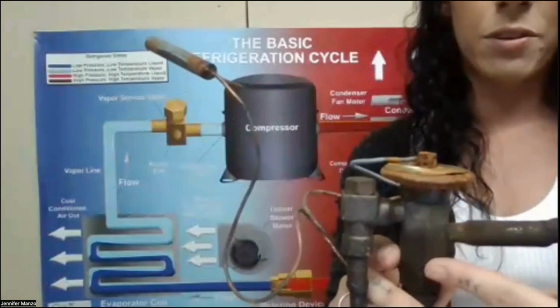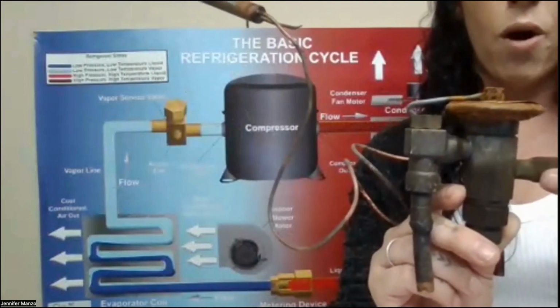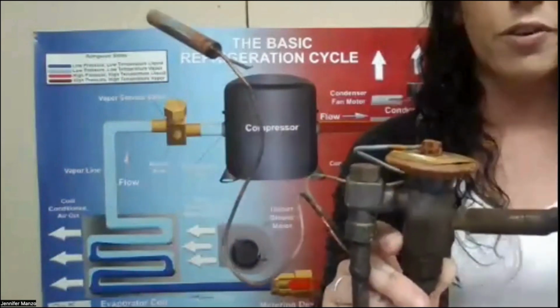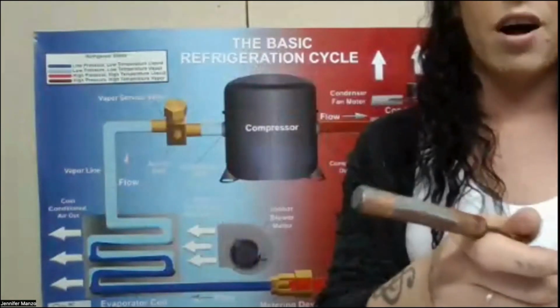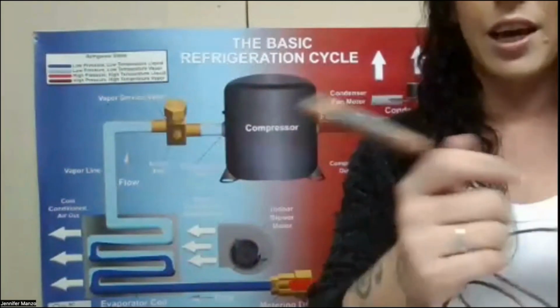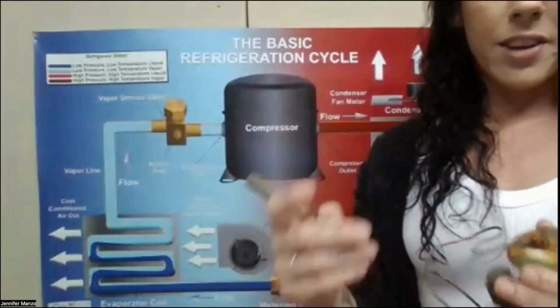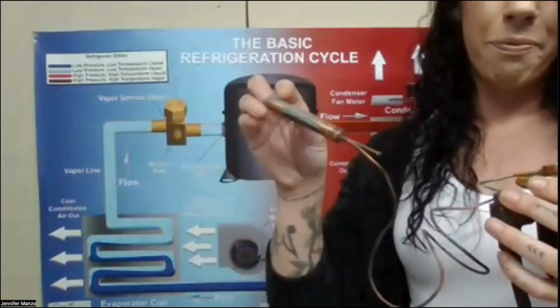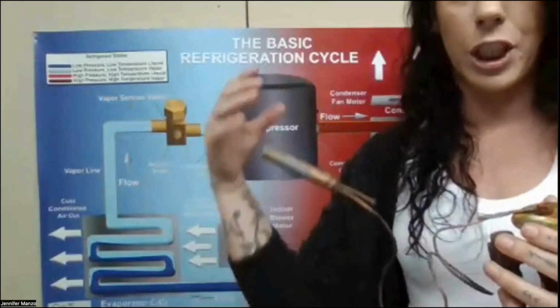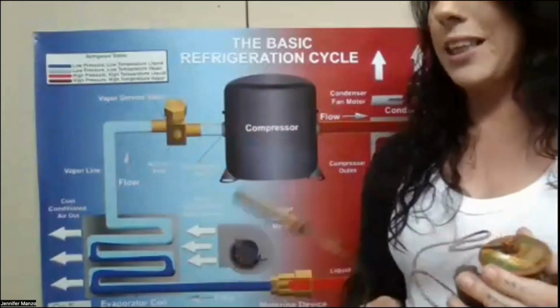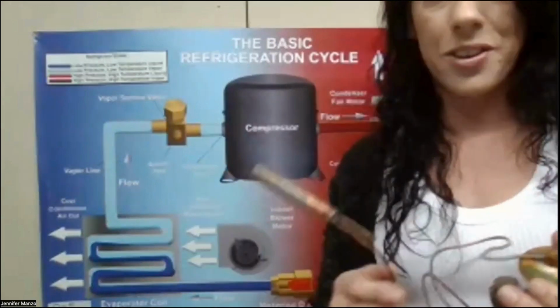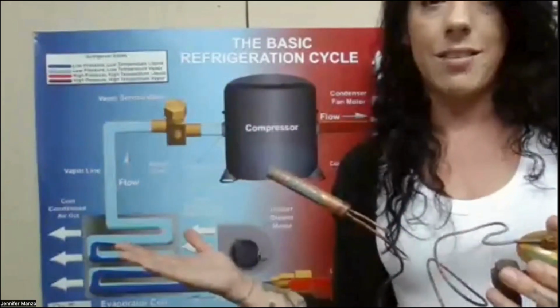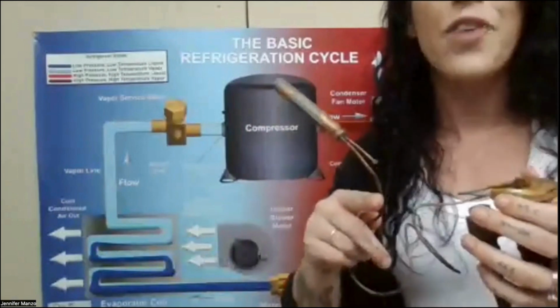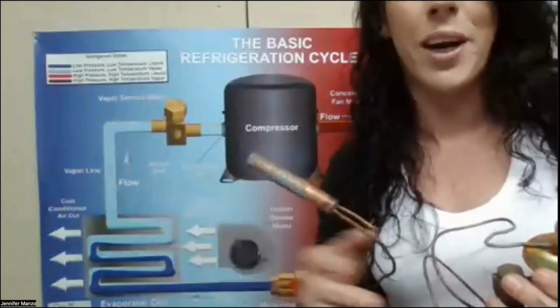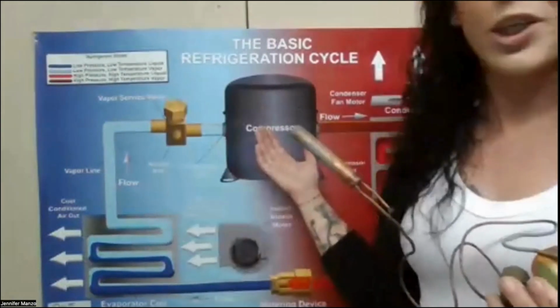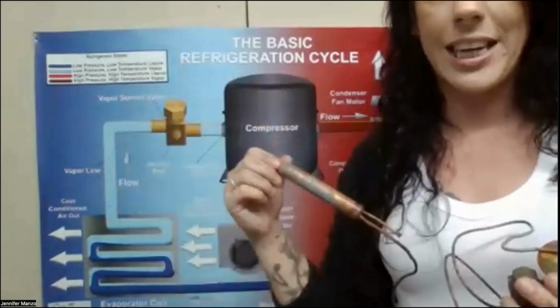The valve moves up and down to let refrigerant out or to not, to either give you more refrigerant or give you less refrigerant. And all of that is based on this sensing bulb. So the sensing bulb goes at the evaporator, and depending on what the evaporator temperature is, the sensing bulb bubbles. It boils, right? Because these refrigerants boil at such a low temperature. So 134A, I believe, boils at almost -15. So if your indoor air is 70 degrees and your refrigerant's boiling at -15, you're going to have saturated boil, saturated vapor. That's going to make it easy for the refrigerant to remove the load from your house because it's going to grab so much heat as it goes through these pipes.